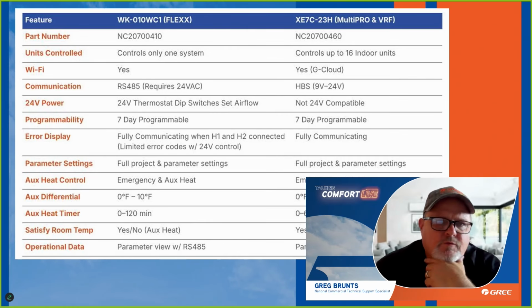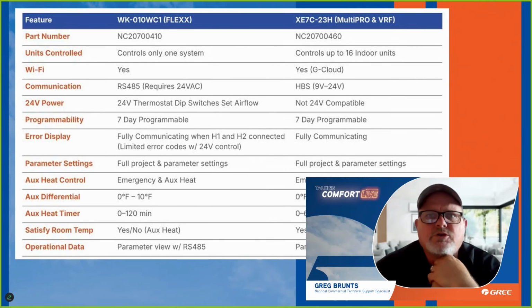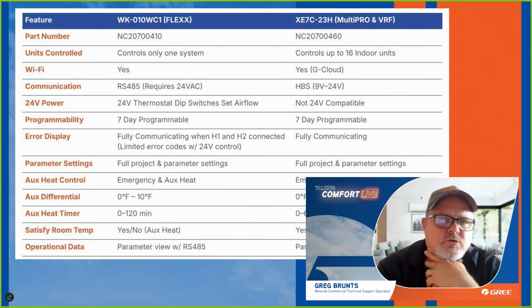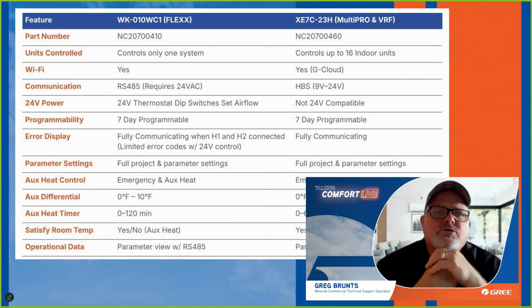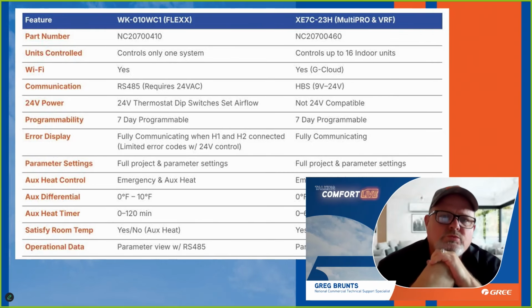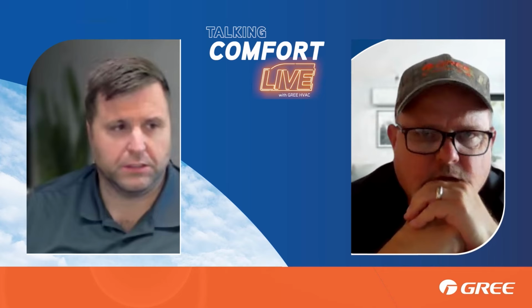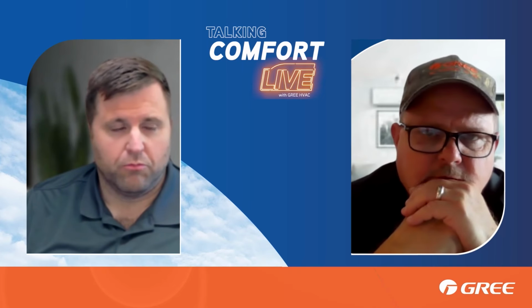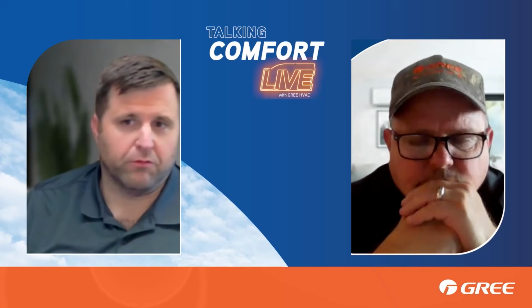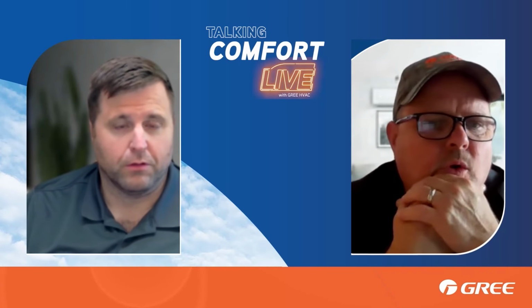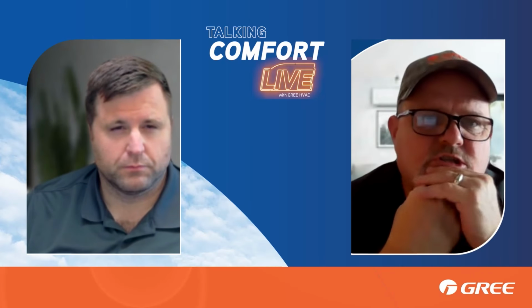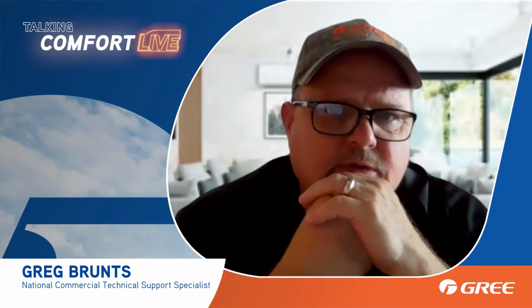Is there a high pressure and low pressure sensor on the FLEXX? Yes, there's a low pressure and high pressure sensor now. It used to only have one pressure transducer, reading high pressure in heating mode and low pressure in cooling mode, but now it has two. On the FLEXX R32, it has two sensors, which gives you a lot more information than you'd ever get out of a standard system. I'm just not sure how much of that is displayed on the controller — we'll mess around with that.